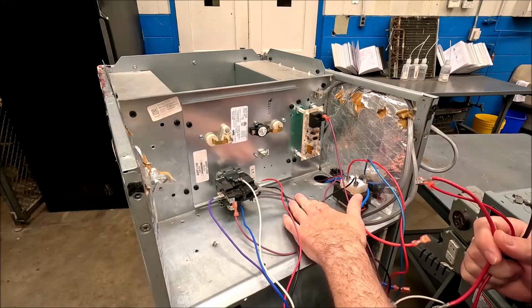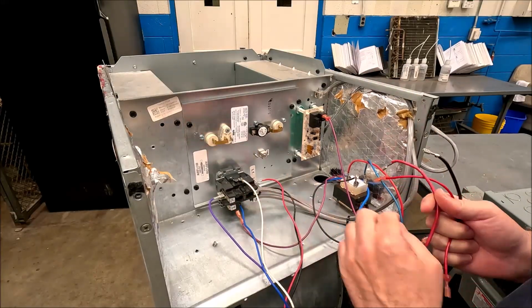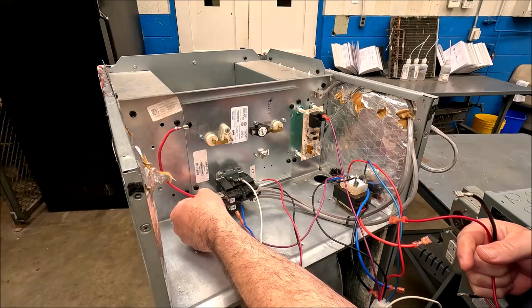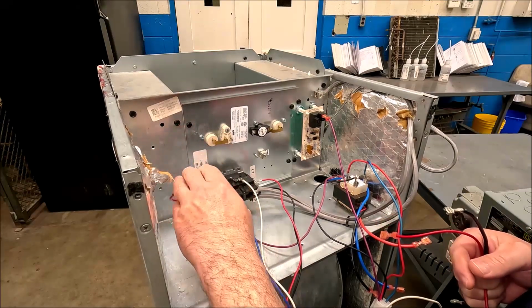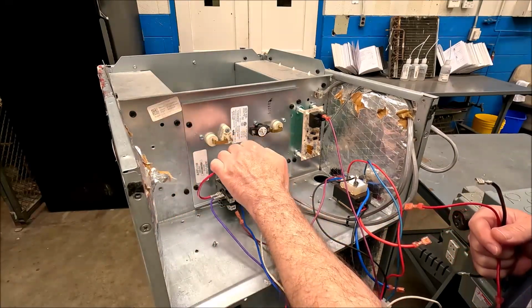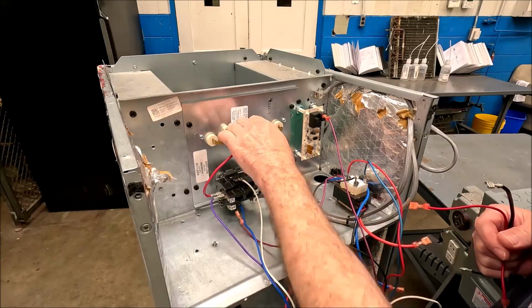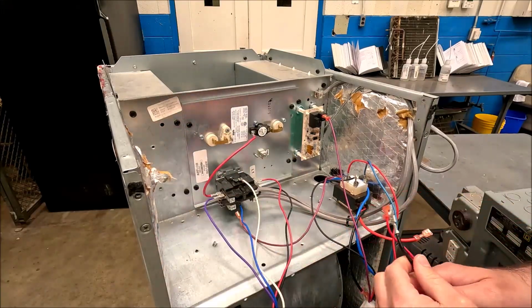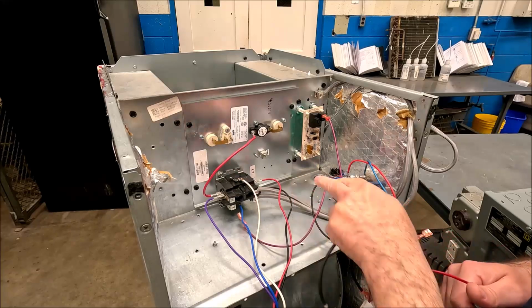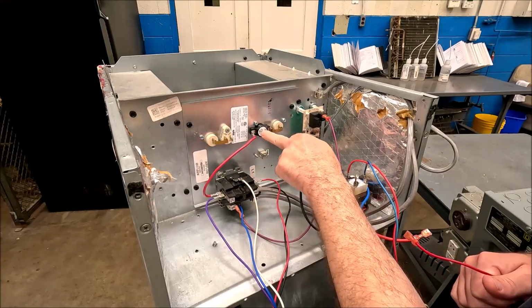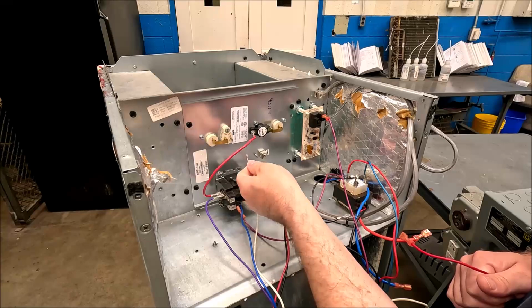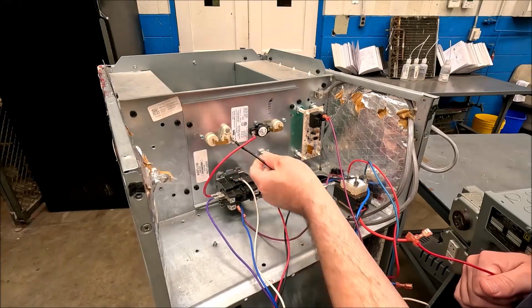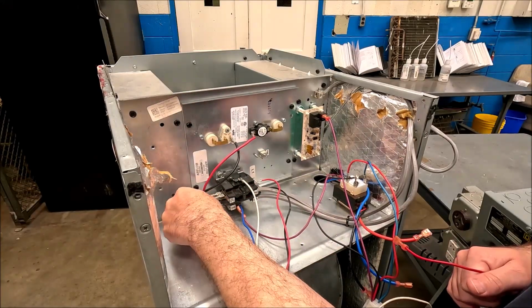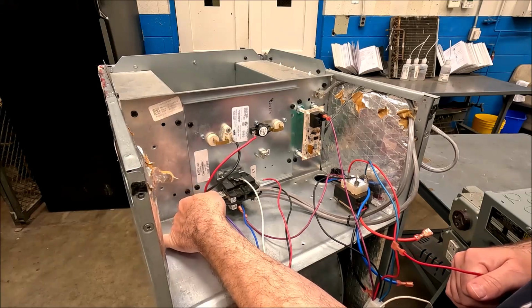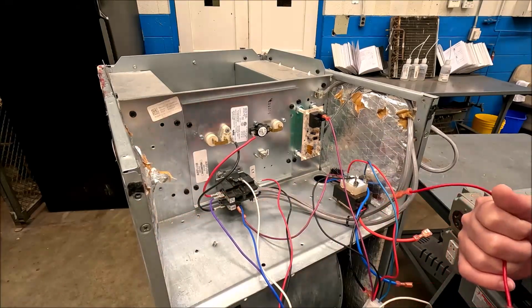So power L1, L2, control is the switch, load. This L1 side, which I've deemed red, is going to go to the heater. That's also where my purple wire is. This black wire here, so power, control to the safeties and the load, and then I return back. So this black wire here is going to go back to the other side of the heat contactor, we'll say, and that's the return path, so that's there.